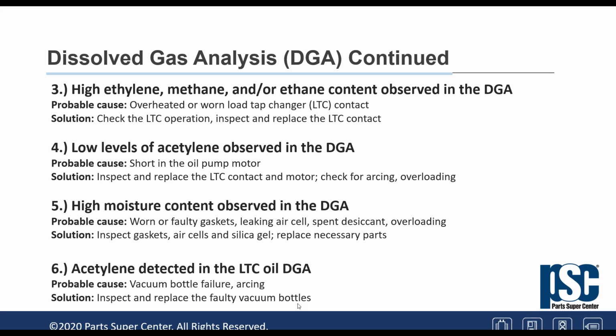Item 5, high moisture content. Again, that's the consequence of something that gets into the oil. Gaskets are the only means we have to seal two surfaces in contact with each other and prevent water or moisture from going in. Also, condensation in the unit can create some moisture, because the unit will cycle through the day, high temperature, low temperature, and that creates some moisture that gets pulled off the fluid in the unit, like oil and so forth. Leaking air cell is another cause. What is an air cell? The purpose of the air cell is to prevent the atmosphere from contacting the oil surface. So if the air cell is defective, we have some oxidation of the oil because it's not being protected, and that's when we have some moisture content in it.